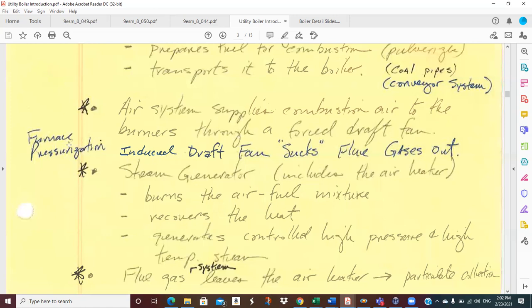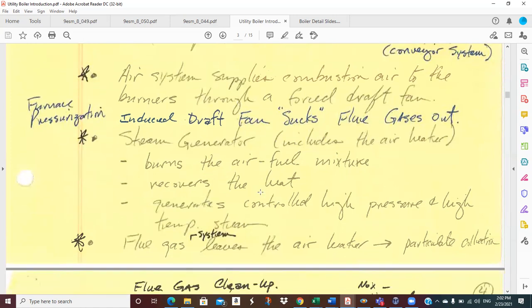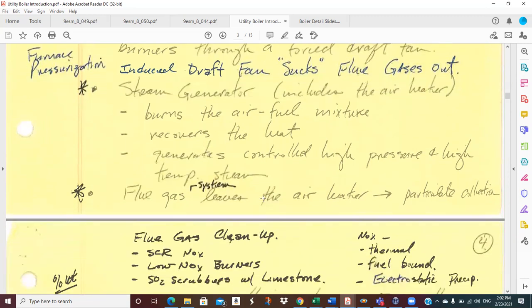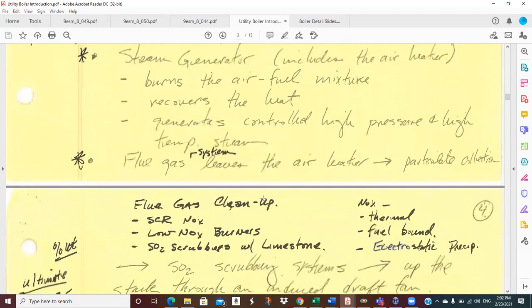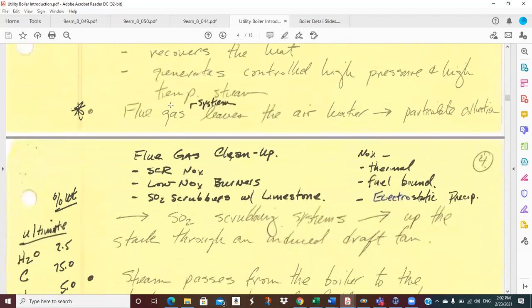Okay, so the furnace pressurization is a balance between how much air the FD fan blows in and how much flue gas the ID fan sucks out. So we can adjust furnace pressurization by adjusting the capacity of those two fans. Steam generator, we're burning fuel, we're transferring heat, we're making steam. We pretty much know what that's all about.